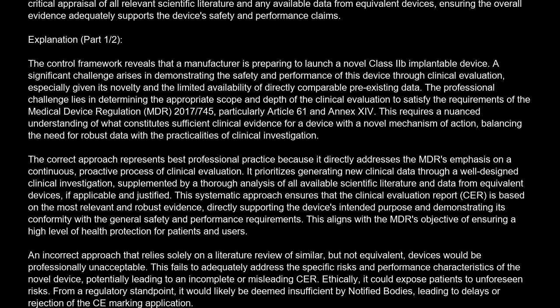The correct approach represents best professional practice because it directly addresses the MDR's emphasis on a continuous, proactive process of clinical evaluation. It prioritizes generating new clinical data through a well-designed clinical investigation, supplemented by a thorough analysis of all available scientific literature and data from equivalent devices, if applicable and justified. This systematic approach ensures that the clinical evaluation report, CER, is based on the most relevant and robust evidence, directly supporting the device's intended purpose and demonstrating its conformity with the general safety and performance requirements. This aligns with the MDR's objective of ensuring a high level of health protection for patients and users.